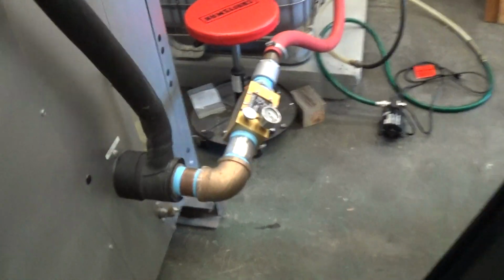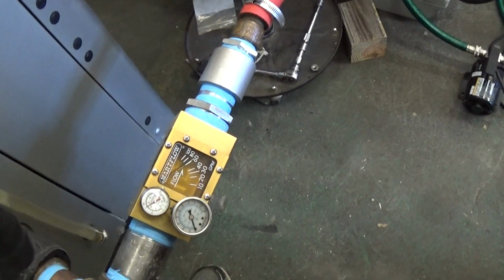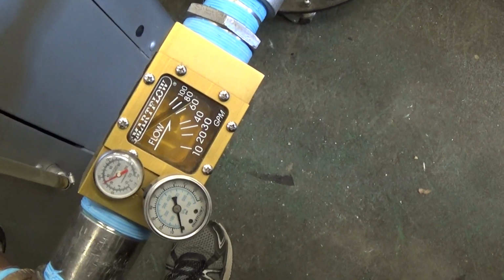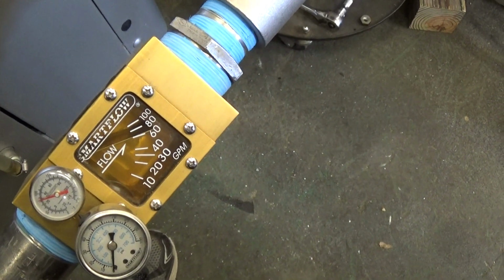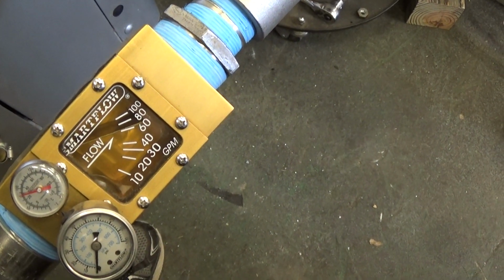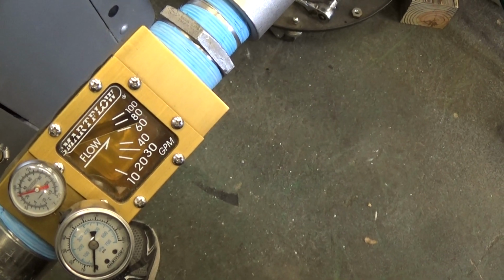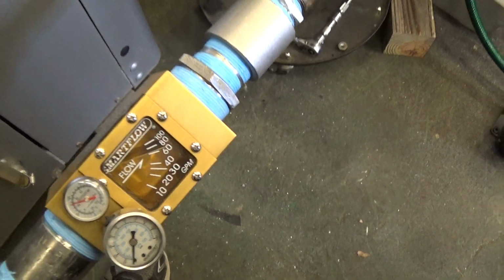The flow, by the way, we have, let's check what our flow is. Yeah, it's right about in that 50, 60 GPM range, which is what you want to see for optimum cooling.